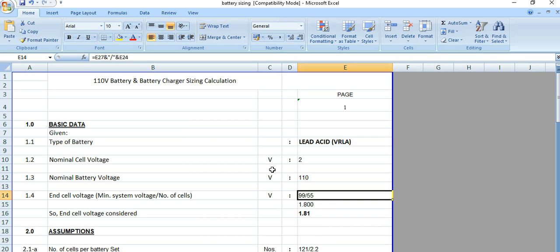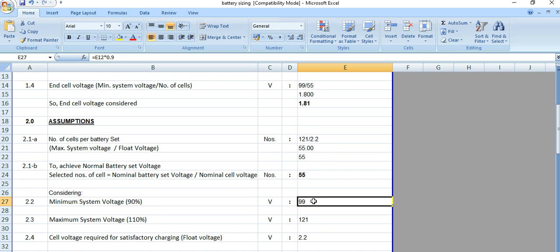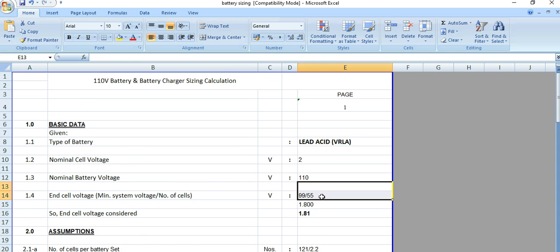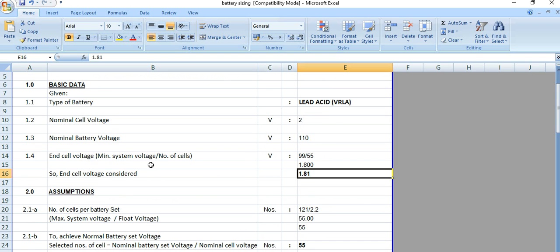The end cell voltage (ECV) is calculated as the minimum system voltage divided by the number of cells. The minimum system voltage value comes from the data below. So end cell voltage equals minimum system voltage divided by number of cells.